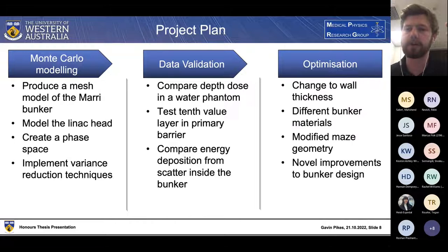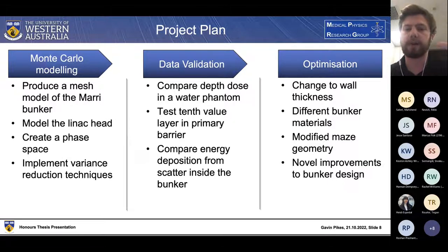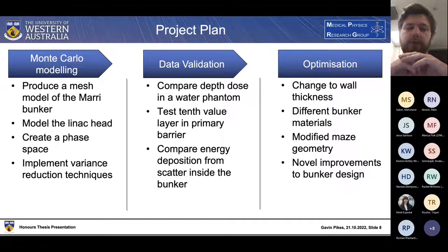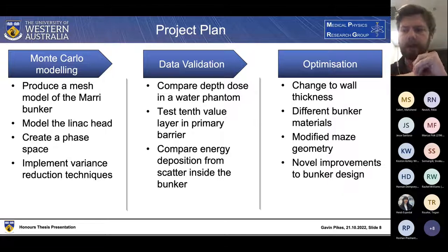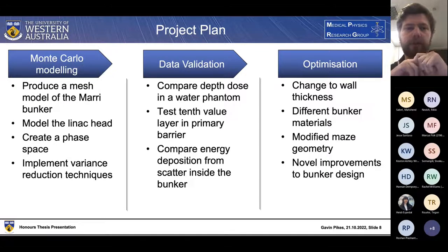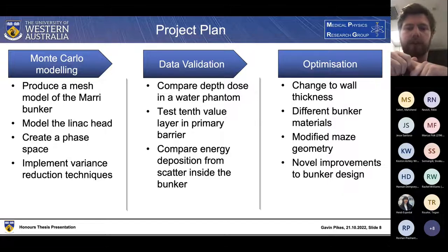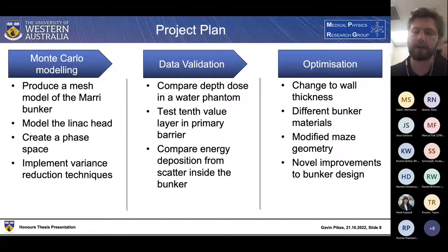The optimisation of the bunker is broken down into four main sections: changes to the wall thickness for both primary and secondary barrier walls; the use of different bunker materials, including higher and lower density shielding concretes; modification of the maze geometry, primarily the width and angles of the triple bend maze; and novel improvements, including the addition of extra shielding layers — a lead layer to the maze, a steel layer to the internal room, and a dual lead-concrete layer.